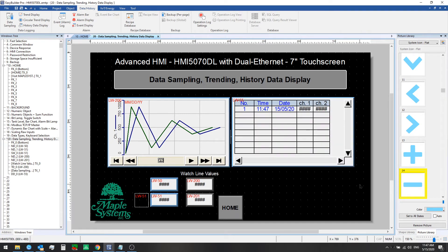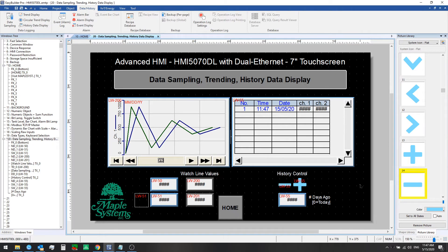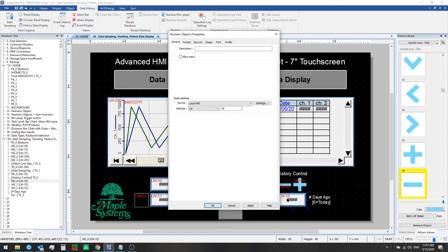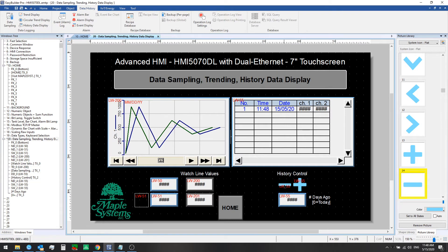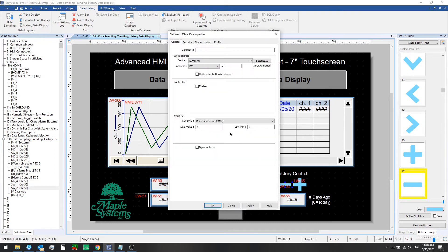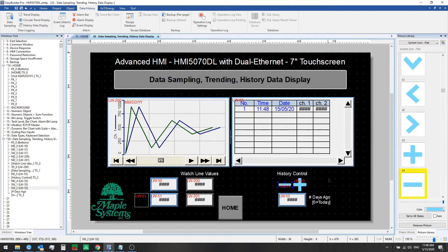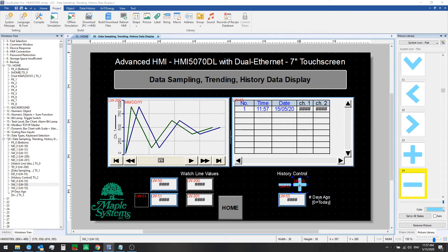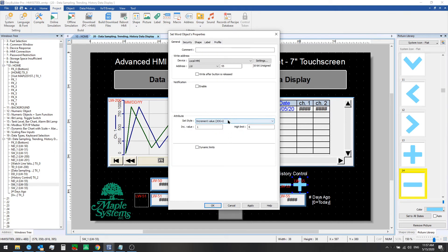We'll also add the history control elements here. What we have is a numeric entry object, so we could directly enter a 0 to show today's data, a 1 to show yesterday's data, and so on. Or we could use the set word object — a decrement jog minus that goes down to 0 as the low limit, or an increment jog plus that increments by 1 up to 6 as the high limit. When the value reaches 6 we would be seeing data from 6 days ago.